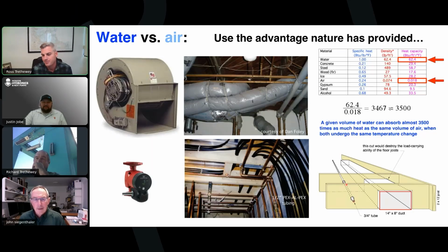Yeah, we've actually been doing some comparisons, air to water versus geo, and both have their place in the market. One of the things we're finding, we call it a COP gap - typically the water to water is going to have a little bit higher COP on an annual basis compared to air to water, but it has a higher cost to put the earth loop in. When you look at return on investment, in many cases the air to water does give you a better return on investment.